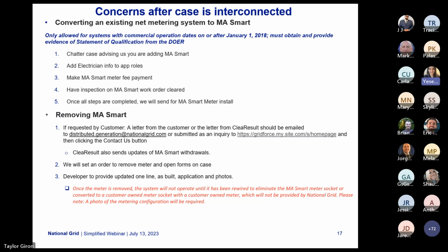If you're removing MA Smart, or we've been notified that MA Smart has been removed from that premise or system, if notified by ClearResult, we'll reach out to you and the customer to let you know. Then we'll go through the process of removing the MA Smart meter and updating all the documents. Keep in mind, once the meter is removed, the system will not operate until it has been rewired to eliminate the MA Smart socket or converted to a customer-owned meter socket with a customer-owned meter.